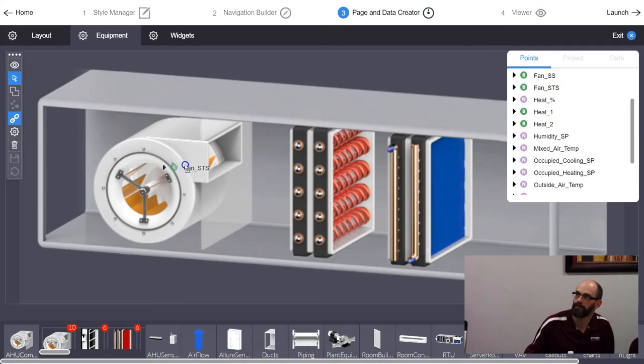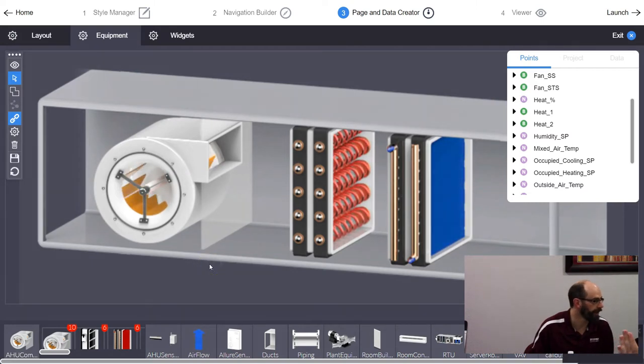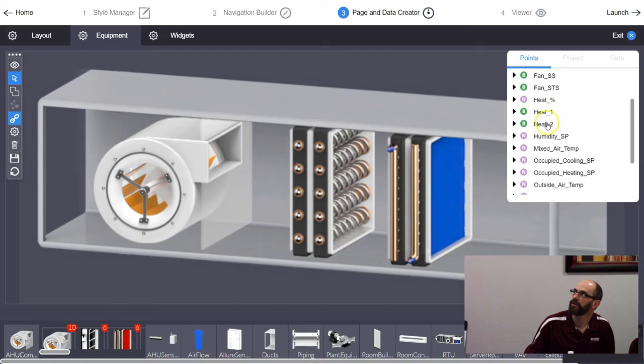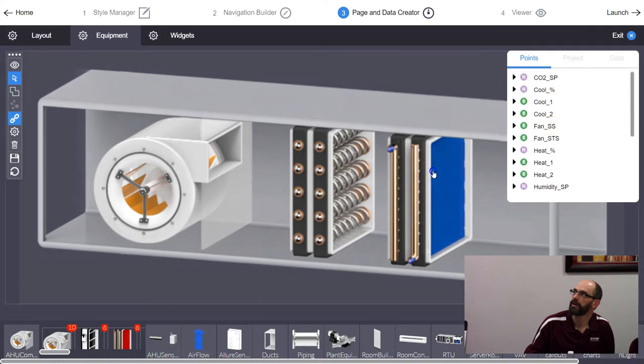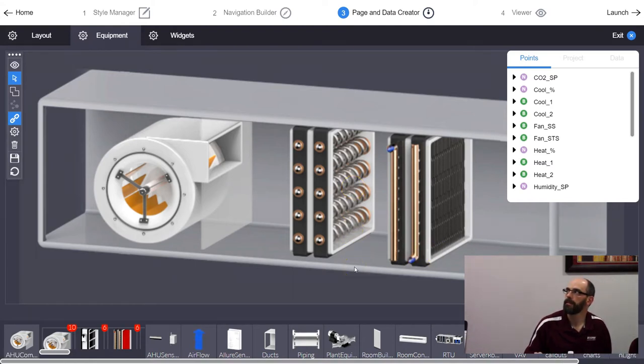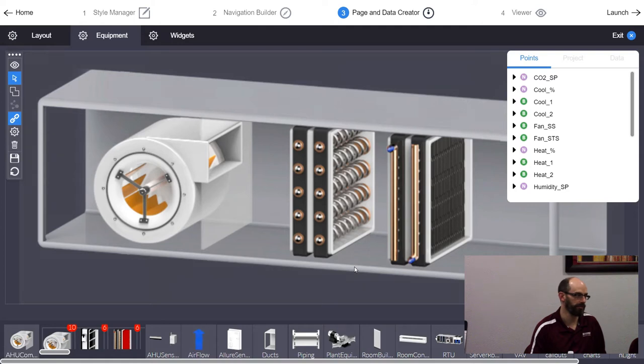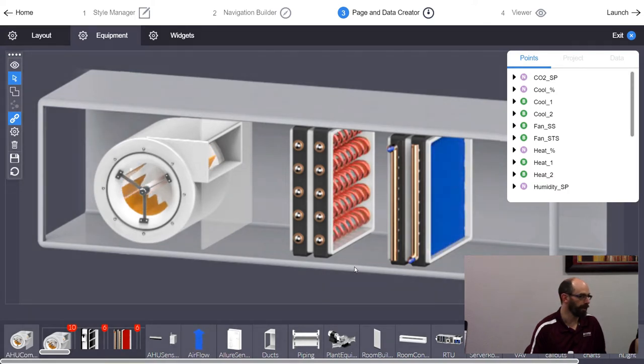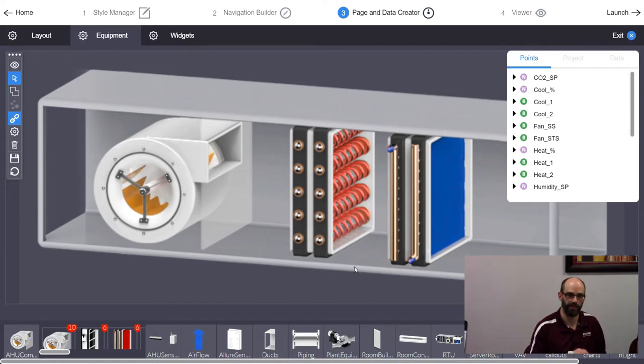To animate the fan to match fan status, drag and drop the fan status point onto it — you'll immediately see it start animating to whatever the current status is. Same for heat — I'll use Stage 1 — and Cooling Stage 1. The animation may appear stopped when the outputs are off, but I have random generators in the background so you should see things kick on and off with staging and status. They're on multi-vibrators and time delays, all slightly different.